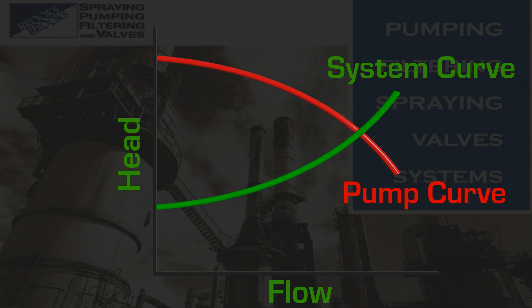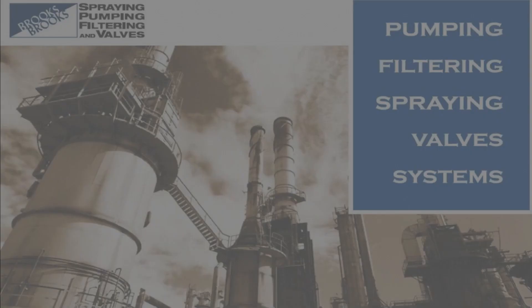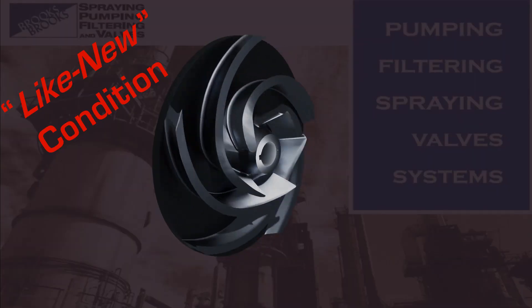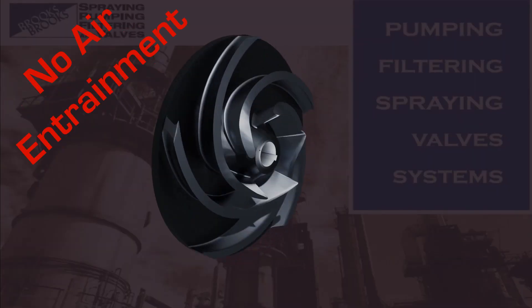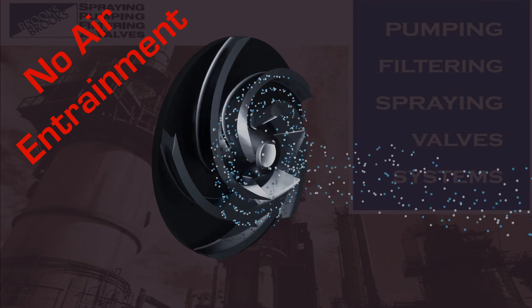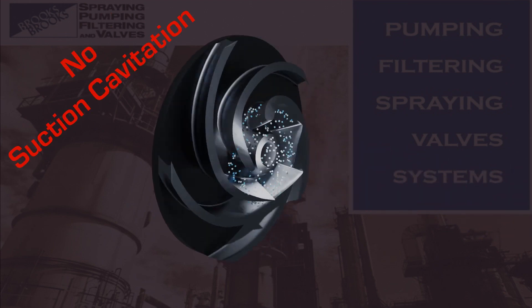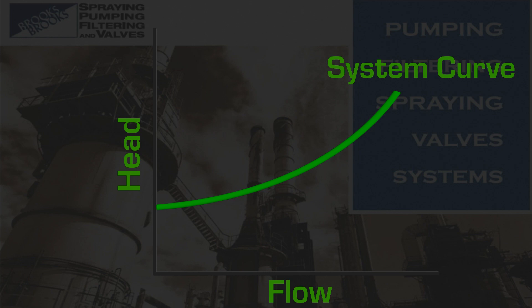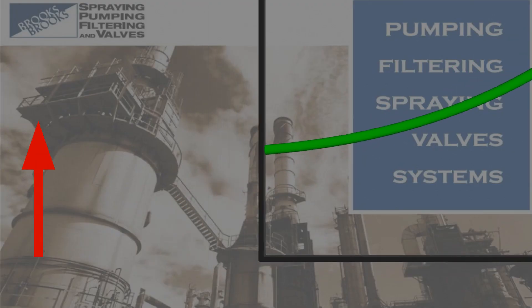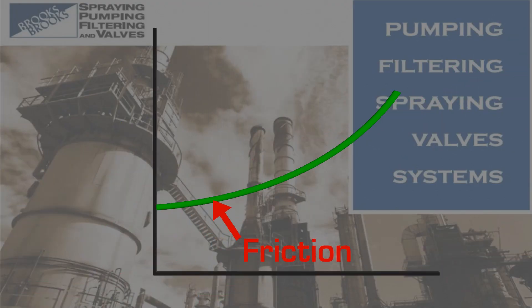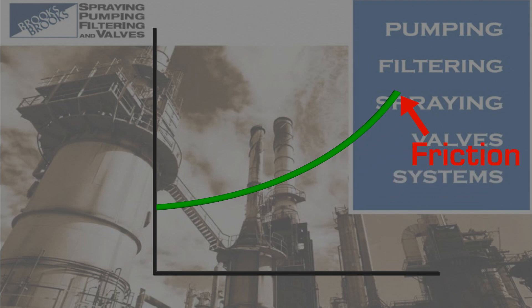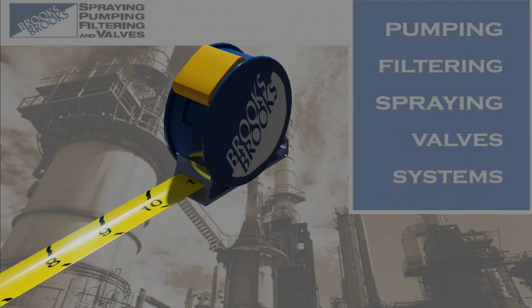Where this curve intersects the pump curve is where the pump should operate. This assumes the pump is in like-new condition, there is no air entrainment, and the pump is not suction cavitating. To develop the system curve, we need to know only two values: the static head and the frictional losses.